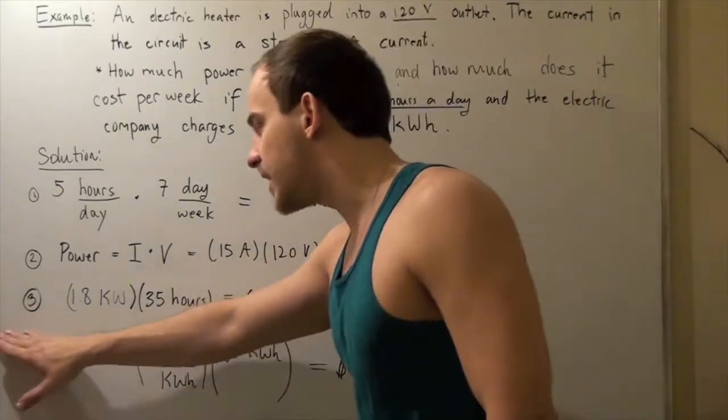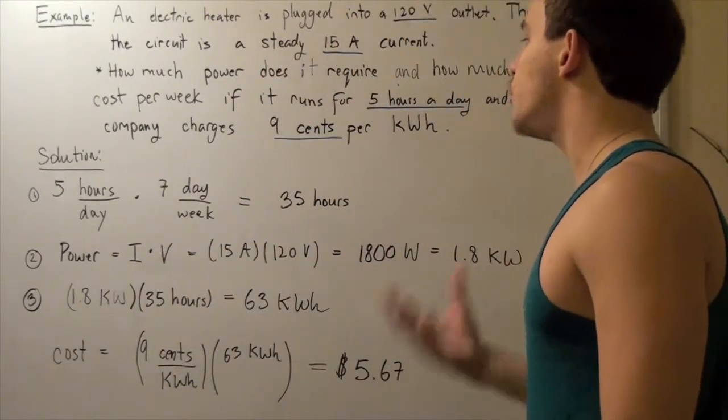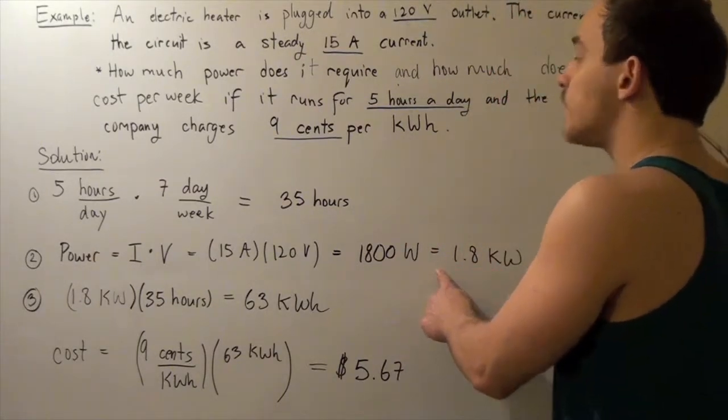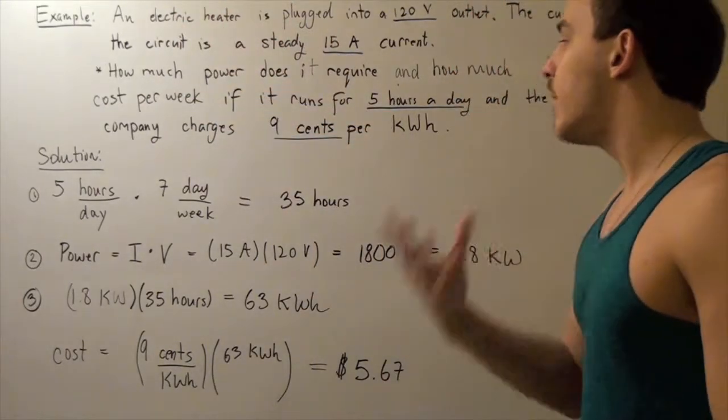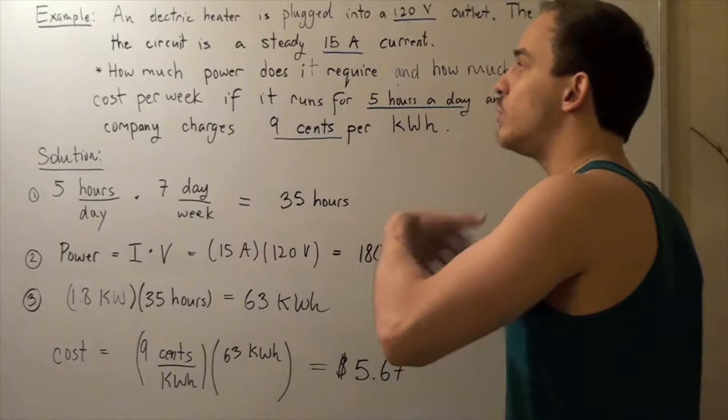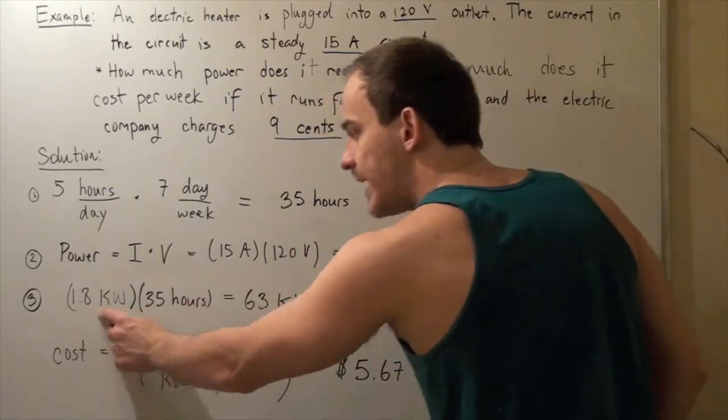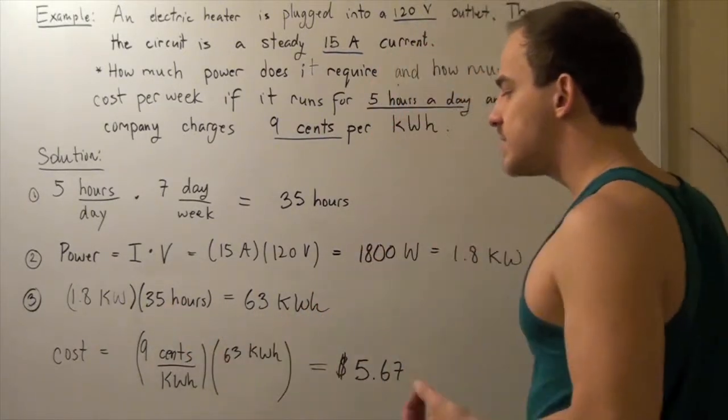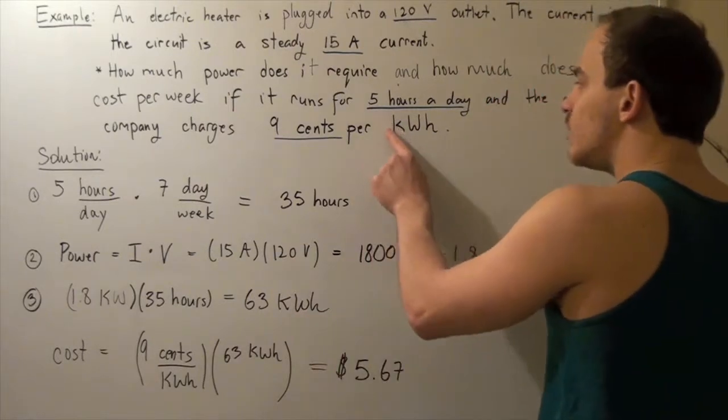In step three, we find how many kilowatt hours are used per week. We take the power required by the heater and multiply it by the hours used per week. 1.8 kilowatts multiplied by 35 hours gives us 63 kilowatt hours.